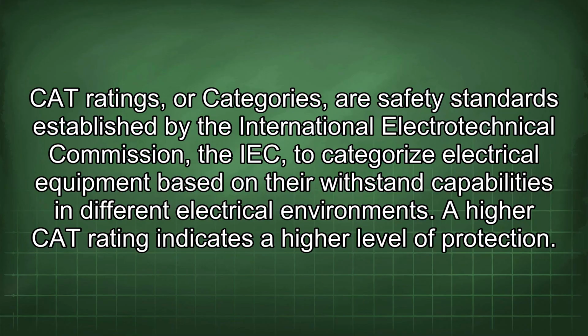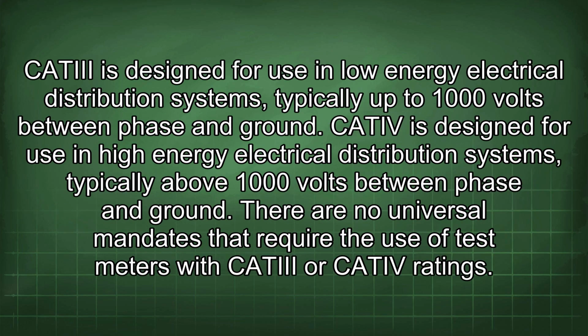CAT ratings, or categories, are safety standards established by the International Electrotechnical Commission, the IEC, to categorize electrical equipment based on their withstand capabilities in different electrical environments. A higher CAT rating indicates a higher level of protection. CAT III is designed for use in low-energy electrical distribution systems, typically up to 1000 volts between phase and ground. CAT IV is designed for use in high-energy electrical distribution systems, typically above 1000 volts between phase and ground.